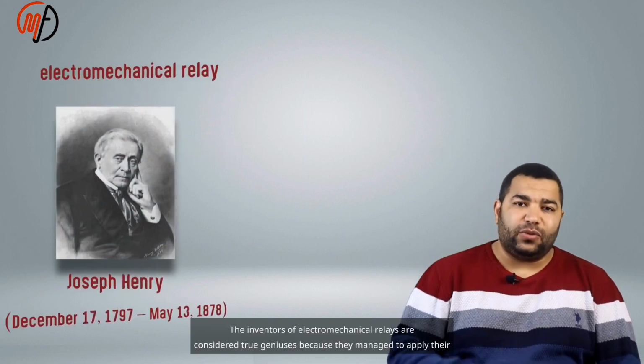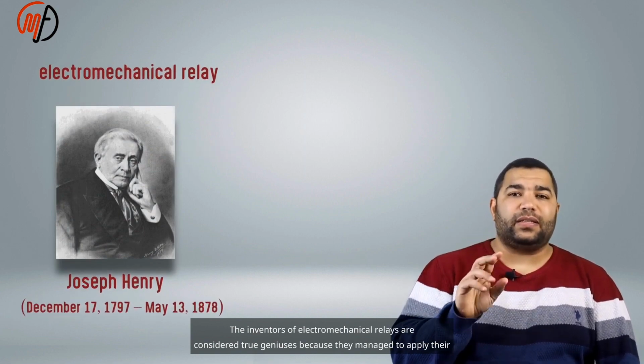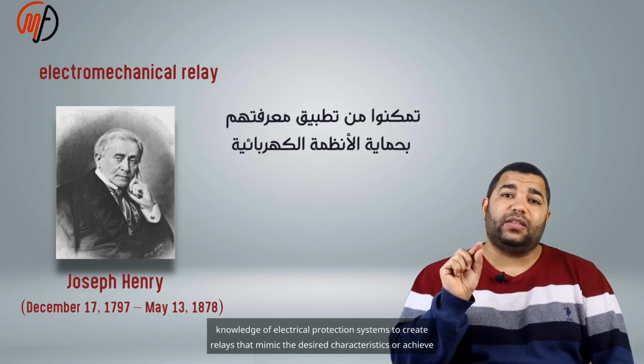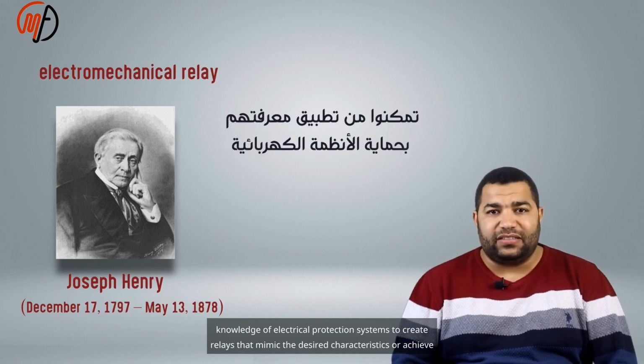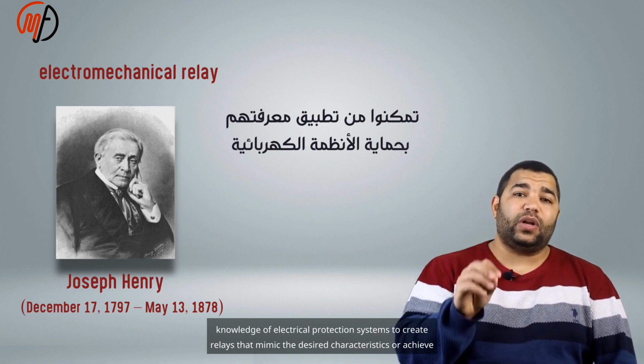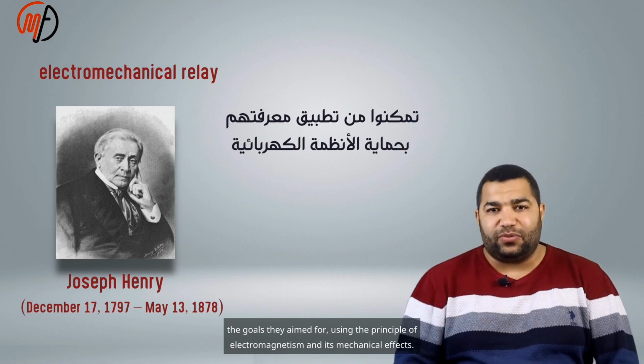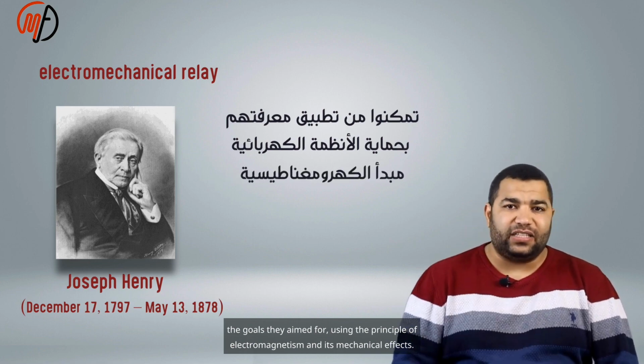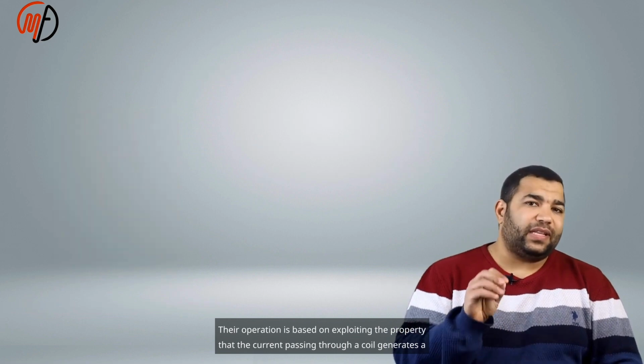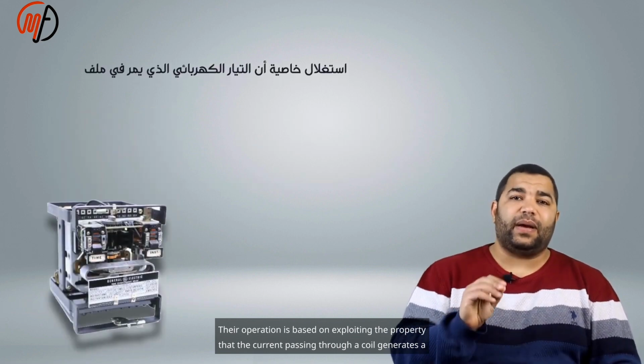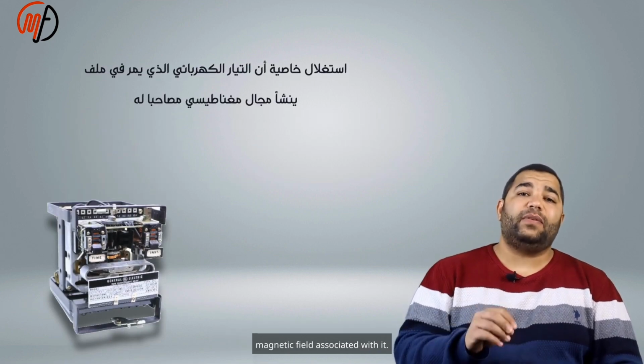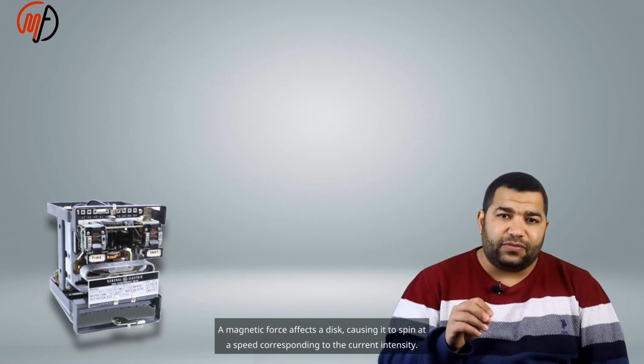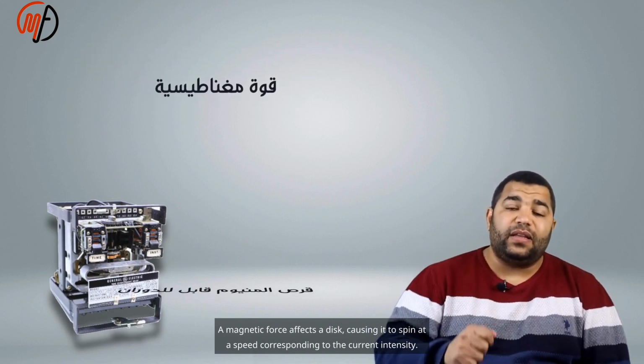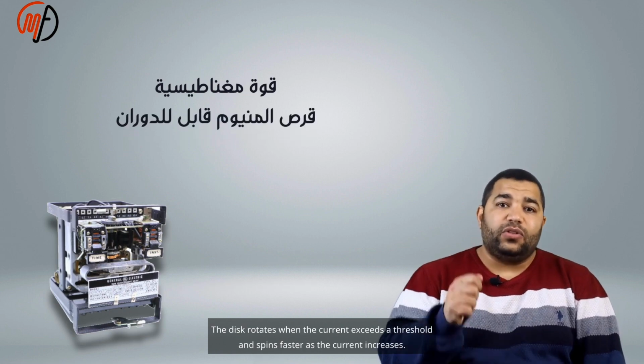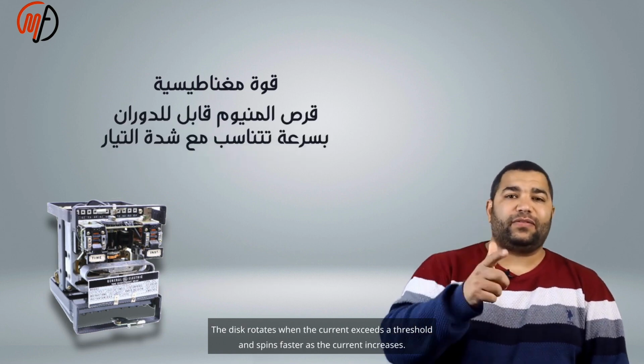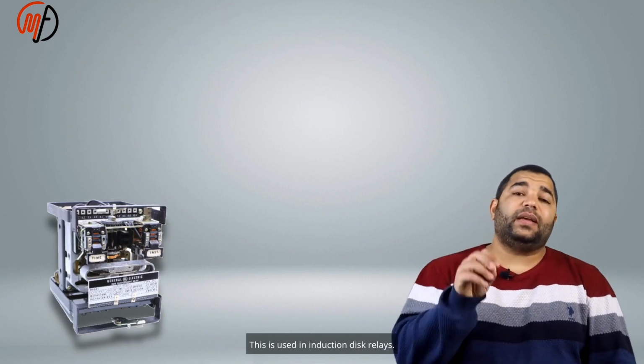The inventors of electromechanical relays are considered true geniuses because they managed to apply their knowledge of electrical protection systems to create relays that achieve the goals they aimed for, using the principle of electromagnetism and its mechanical effects. Their operation exploits the property that the current passing through a coil generates a magnetic field. A magnetic force affects a disk, causing it to spin at a speed corresponding to the current intensity. The disk rotates when the current exceeds a threshold and spins faster as the current increases. This is used in induction disk relays.